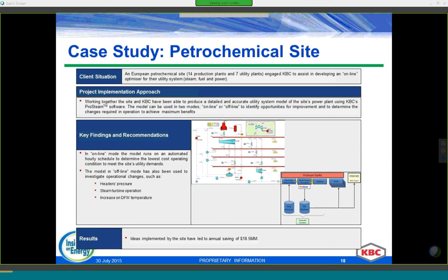Another interesting point from this case illustrates the hidden benefit of building a model: while the model was being built, several ideas were suggested, and once the model was ready they were tested. Some ideas explored included: increasing the pressure of the very high pressure header and decreasing the pressure of other headers — a benefit of about $2.5 million per year; optimization of the turbines, mainly focusing on reducing condensing operation — adding an impressive $15 million per year; and changes to increase the demineralized water temperature — a lower but still significant saving of around $600,000 per year.